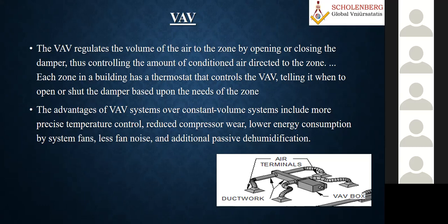So each has a thermostat, and that controls the VAV. VAV itself is another subsystem from the air handling unit. That means at the terminal level. So in the VAV system itself, we have a thermostat and the controls, and those controls can also be connected to the building automation. So that senses, and the building automation senses and regulates. It's a partial load, full load. Depending upon that, the control sends the signals, and it opens the damper.